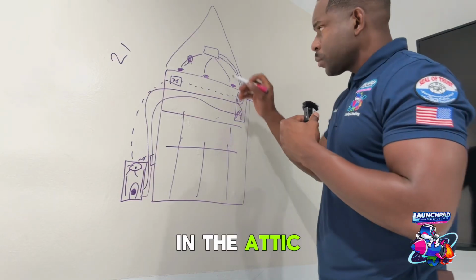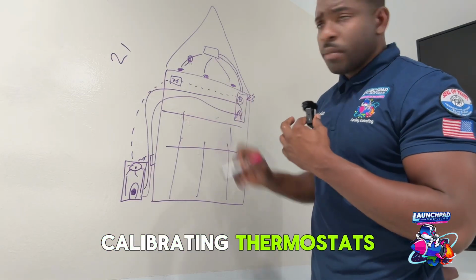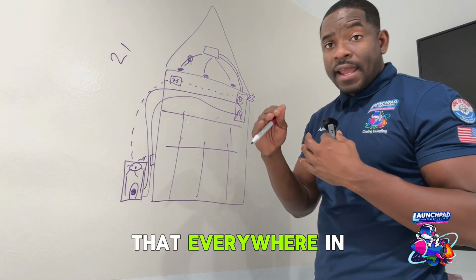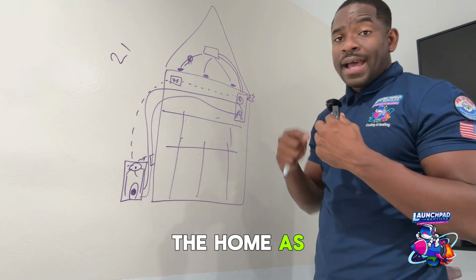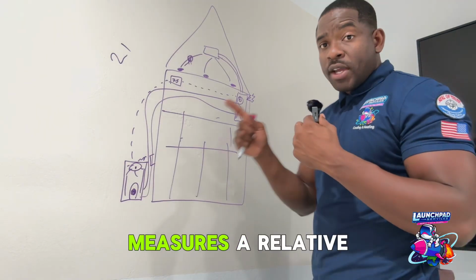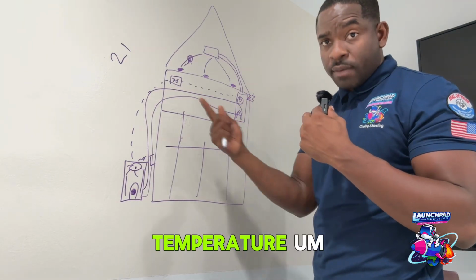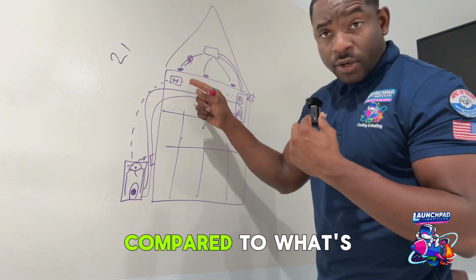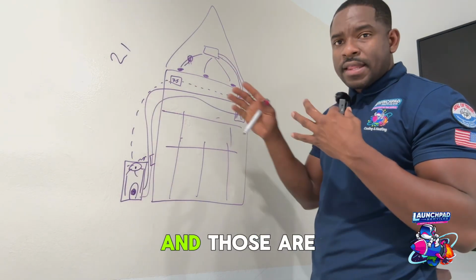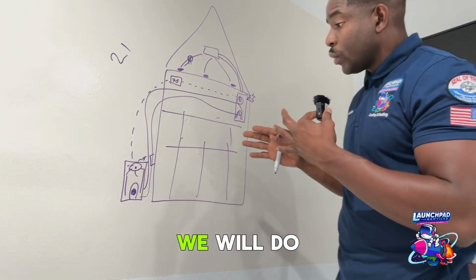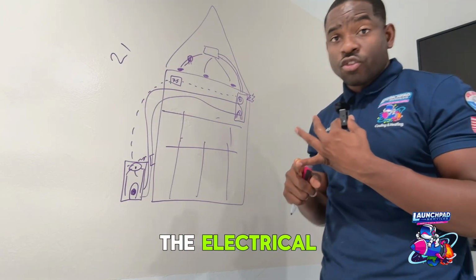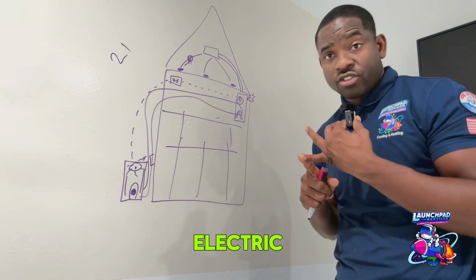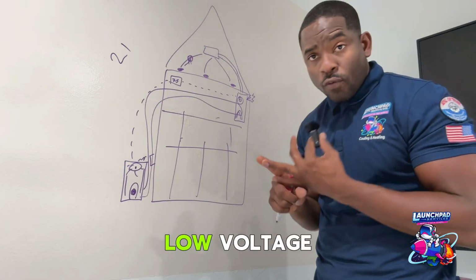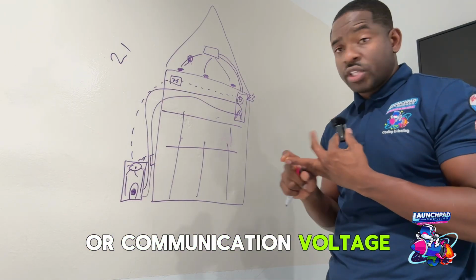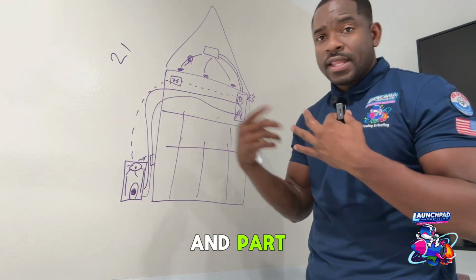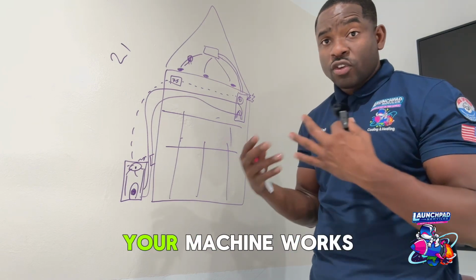And again, we're calibrating thermostats. We're making sure that everywhere in the home, as much as possible, measures a relative temperature compared to what's at the thermostat. And those are the calculations that we will do. We're also checking the electrical. What if we're not getting sufficient electric, high voltage or low voltage or communication voltage to each piece and part? That impacts the flow of how your machine works.